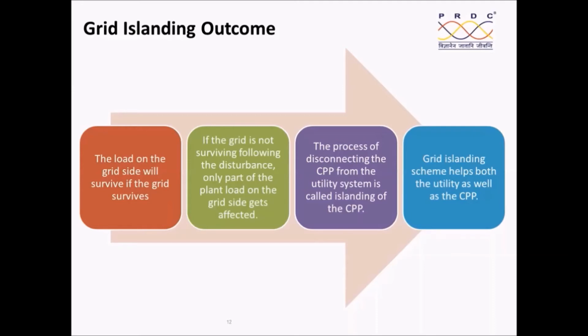The process of disconnecting the CPP from the utility system is what we call islanding of the captive power plant. In an industrial system, there can be one main island, that is the grid and also the entire process plant getting islanded. That is the main islanding scheme. And there can be a sub-islanding scheme also. In the sub-islanding scheme, whenever there is a major disturbance, and with the main islanding scheme the grid or the captive power plant doesn't survive, it may so happen that the CPP, along with some essential load, a part of the CPP, there can be 2 or 3 generators, a part of the generators along with their essential load can get separated out. That is what we call sub-islanding.